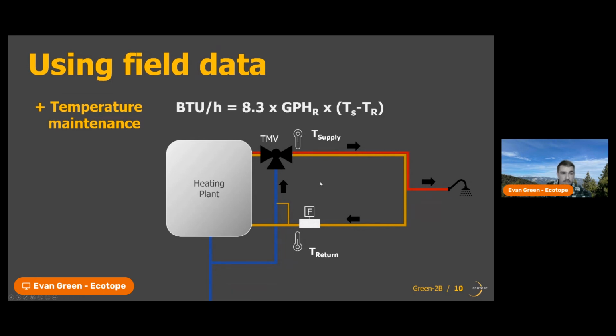So we're basically saying that this water is heating up by the time it gets to the return, which we know is not happening, but we need to make sure to account for that and not just take instantaneous readings in these buildings. We need to take readings over a longer period of time and then average those readings out to make sure we're accounting for those variations in mixing valve temperatures.